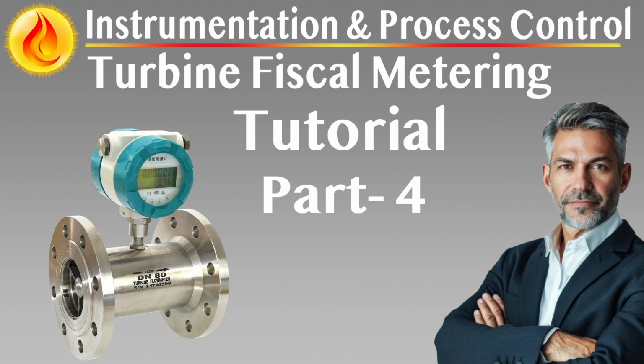All pulse inputs must be digitally filtered to reject noise while preserving accuracy. Input signals must include detector switch activations, prover inlet and outlet temperatures, prover pressure, valve position and seal integrity status, raw turbine meter pulses. Output signals must include stream control valve commands, prover four-way valve actuation, serial data exchange with stream and station microcomputers. Alarm and validation report generation.